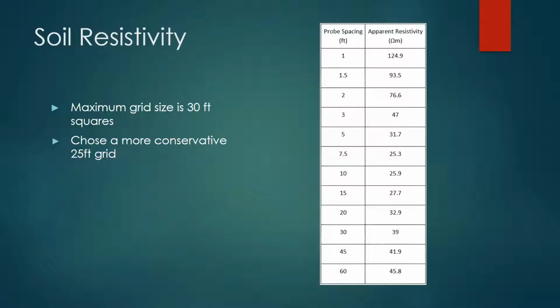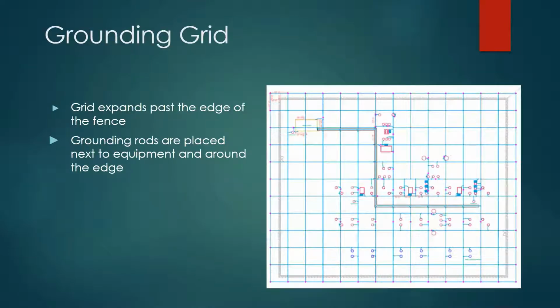Using our soil resistivity chart, we found out that a maximum grid size would be 30 feet. We chose a more conservative 25-foot grid to maximize safety. Here's a preliminary design of our grounding grid. The grid expands past the edge of the fence to get fault currents away from the substation as quickly as possible. The purple dots are grounding rods, which are 20-foot long rods pounded into the ground. These help to get fault currents deep into the soil where it's less resistive.